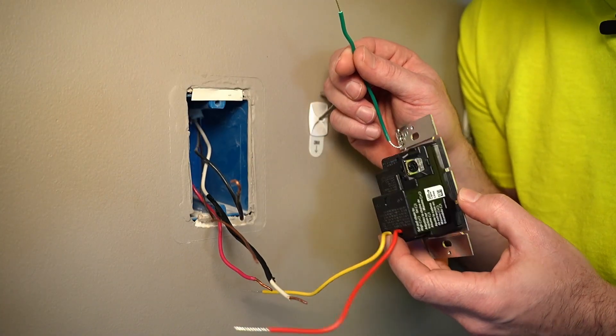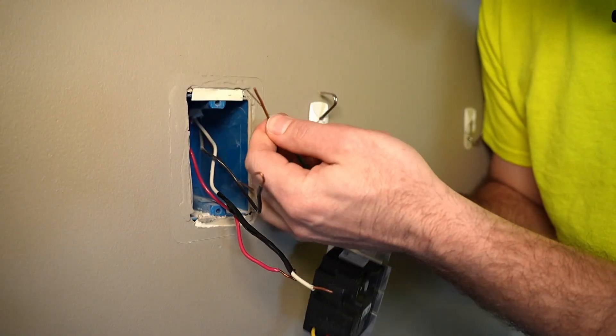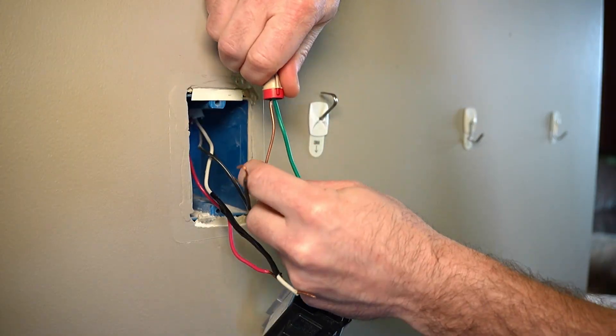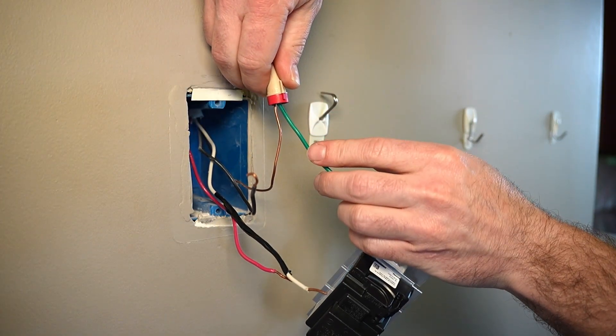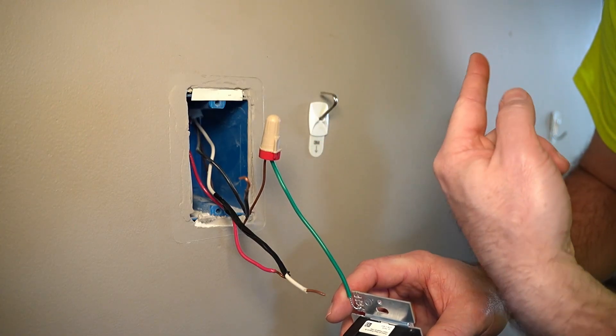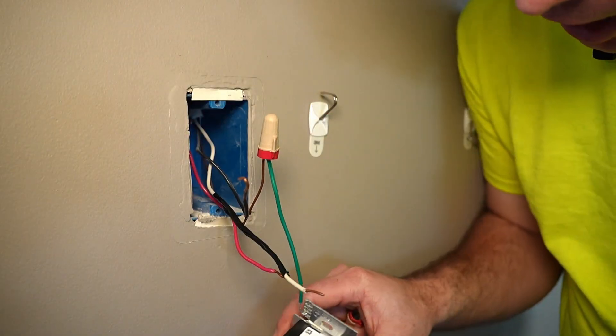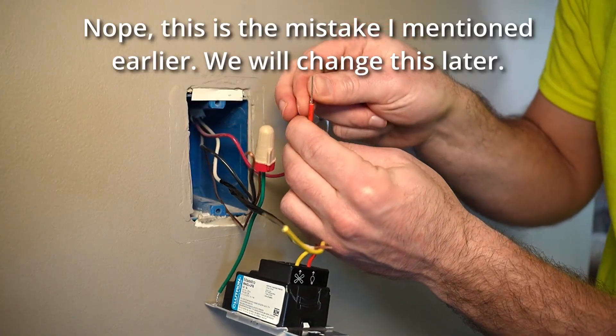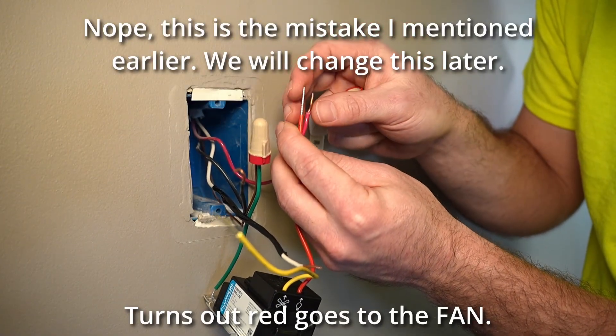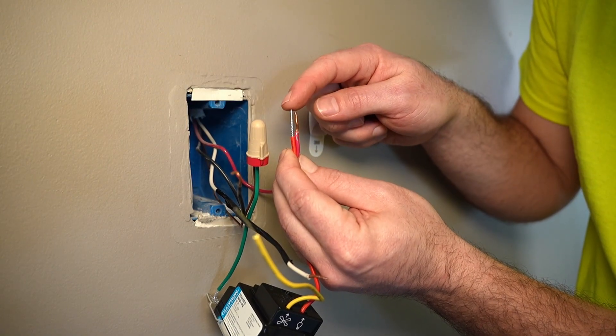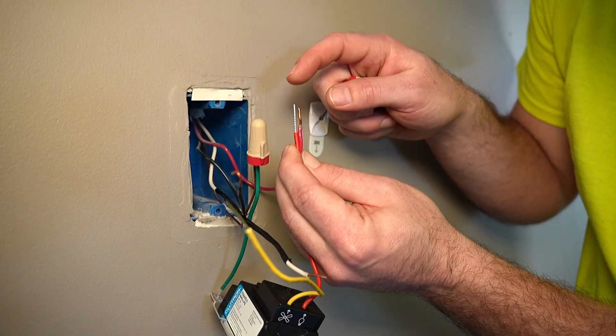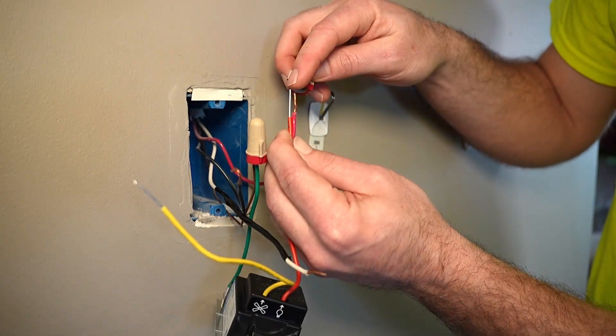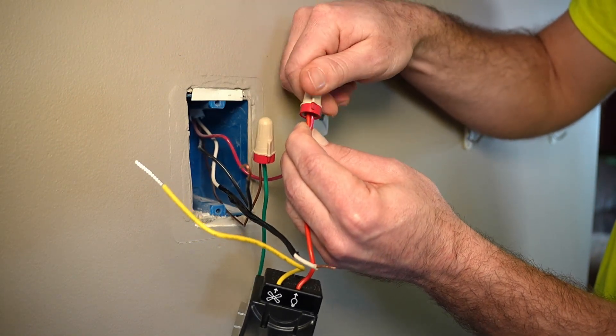So we'll go ahead and put our loop on. My personal preference when actually installing devices is I like to land the grounds first. Is there really a reason for that? Maybe not. I like to do it just in case something goes wrong while I am installing it. Always give the wire nuts a tug check just to make sure those wires don't come out. If you're wondering how to use wire nuts properly, check it out. I've got a video right here on how to use wire nuts. Now remember, we already saw that this red wire is actually going to connect right back up to this red wire. And this red wire here is actually what's responsible for powering up the lights up in the fixture. Because the 14 gauge here is a little bit bigger than this fixture wire right here going to the device, I'm actually going to put this little fixture wire up just a little bit farther.